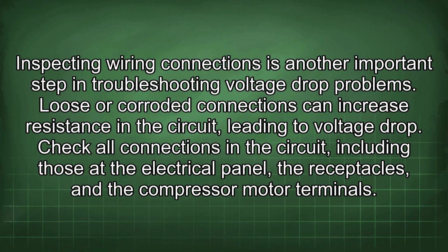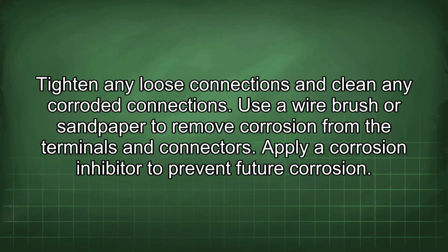Loose or corroded connections can increase resistance in the circuit, leading to voltage drop. Check all connections in the circuit, including those at the electrical panel, the receptacles, and the compressor motor terminals. Tighten any loose connections and clean any corroded connections. Use a wire brush or sandpaper to remove corrosion from the terminals and connectors. Apply a corrosion inhibitor to prevent future corrosion.